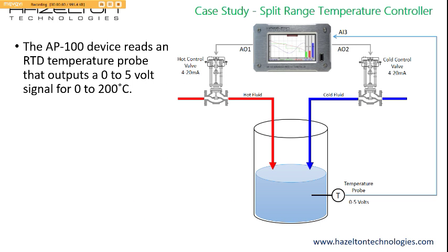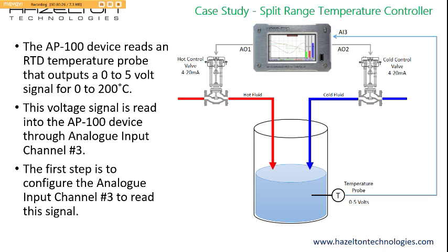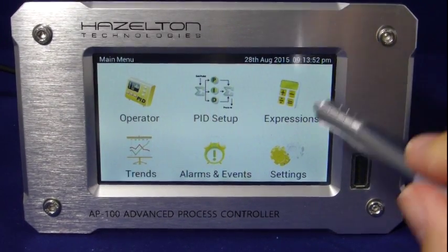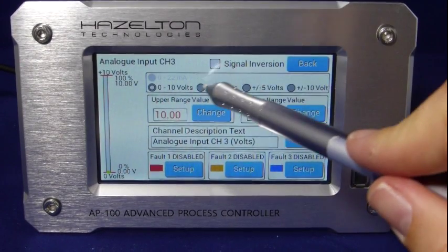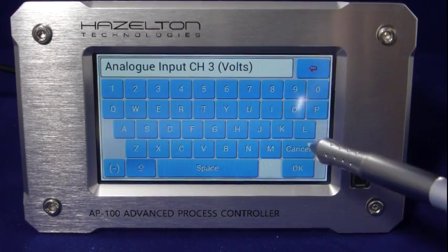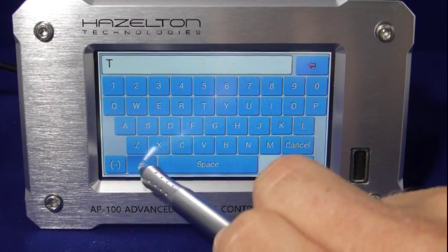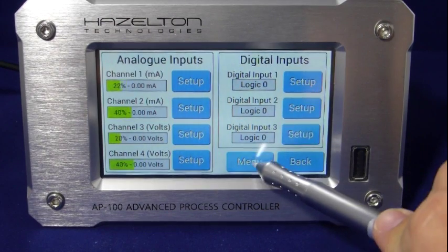The AP100 reads the fluid temperature from an RTD probe outputting 0 to 5 volts for 0 to 200 degrees Celsius, connected through analog input channel 3. To configure it, press the settings icon from the main menu, then press input channel setup, then channel 3 setup. Change the voltage range to 0 to 5 volts, then press the change button on the channel descriptor text field. Press backspace to delete the default text, enter the desired descriptor, and press OK to accept the changes, then navigate back to the main menu.